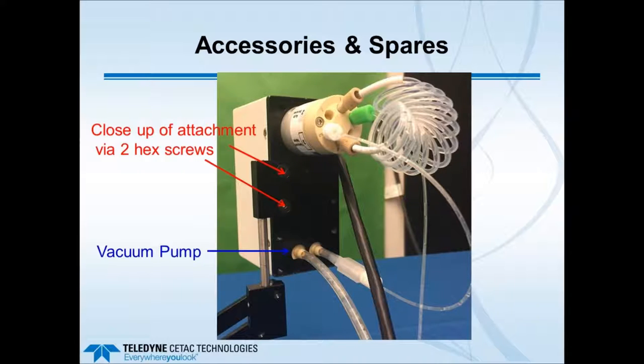Two hex screws on the anodized aluminum front are inserted through two holes in the block to connect the Articulating Mounting System to the valve pump module, enabling you to maneuver and place it as close to the host nebulizer as possible. The blue arrow calls out the connections to the vacuum pump—two barbed connections through which sample flows around the sample loop and out to waste.